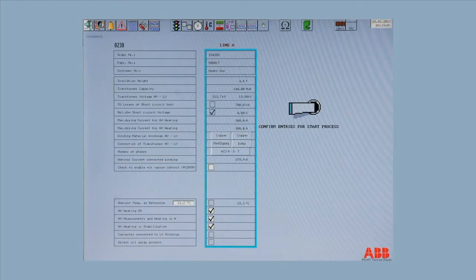Before the processing can take place, certain critical information about the transformer being processed must be entered into the system. The first 3 lines just contain identifying information. The insulation weight is an important number and must be entered as accurately as possible. The insulation weight is used by the process to calculate the amount of water lost during processing. The remaining values are also used in the process, and any error in any entry may result in damage to the transformer.